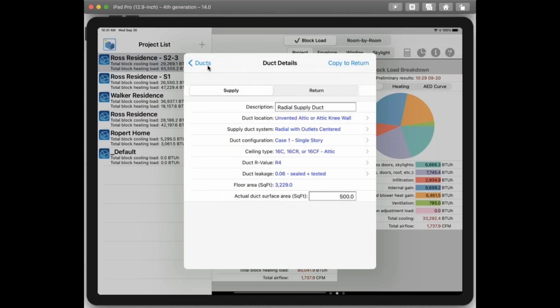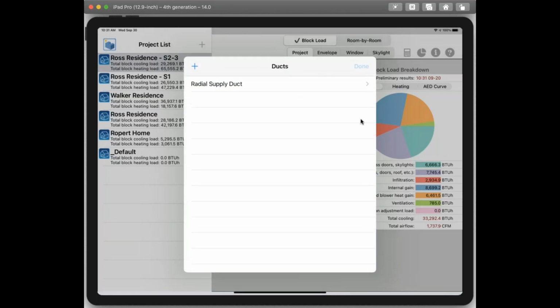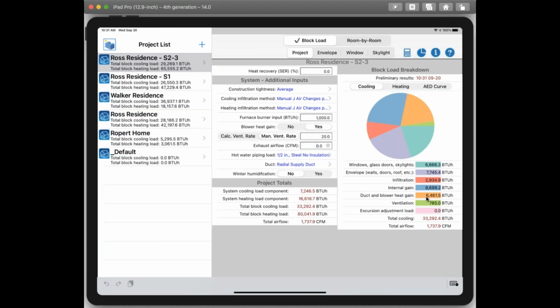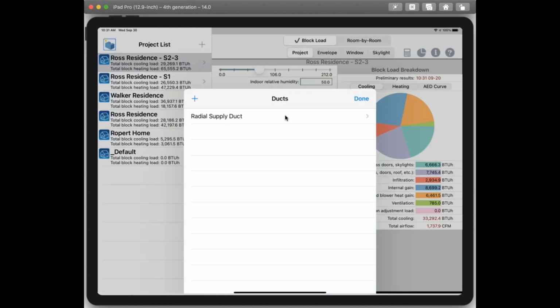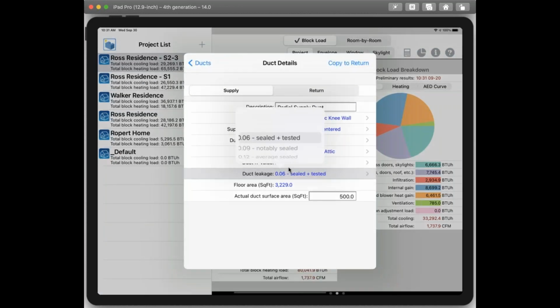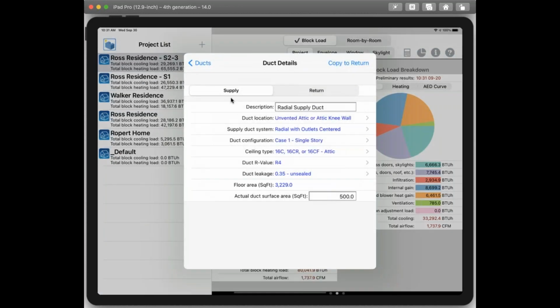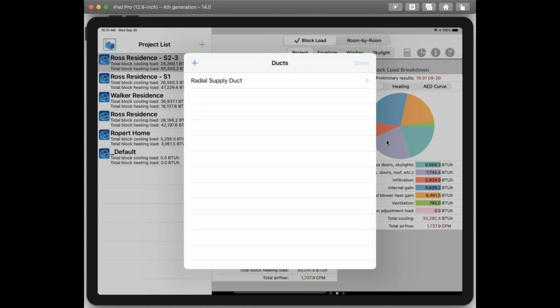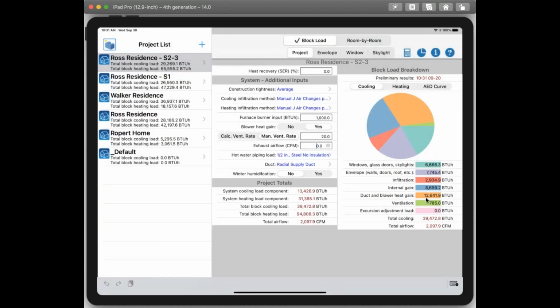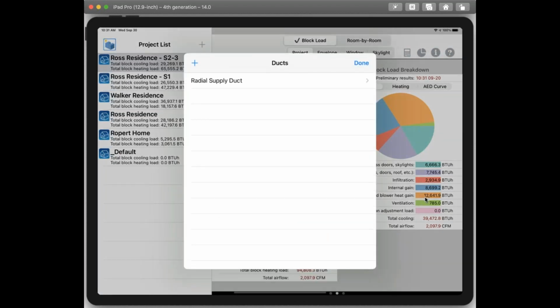If I close this real quickly, you'll see that my duct heat loss is about 6,400. It includes blower heat gain, but that's minimal. So let me go back in here and change this to a leaky duct system. You'll see that an unsealed duct system pretty much doubles my duct load. So it's really important that you get this correct, because it could dramatically affect your total cooling load and also your heating load.